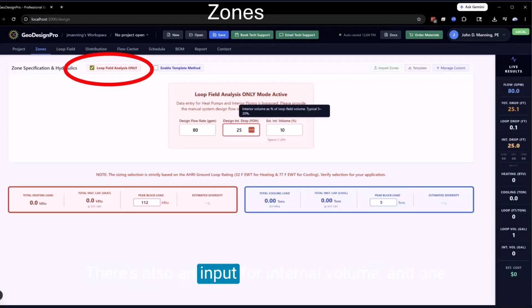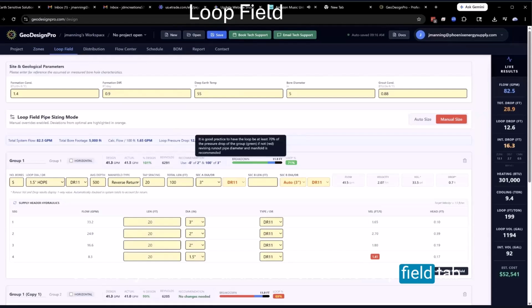There's also an input for internal volume. And one thing you'll notice with our software, we have tool tips. Here's one that pops up on the internal volume. It's a percent of loop field volume. Anywhere from 5 to 20% is pretty typical, so you put a percentage in there that's reasonable. Once you do this and move on to the loop field tab, you can define your loop field.